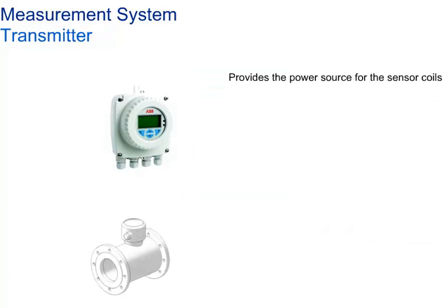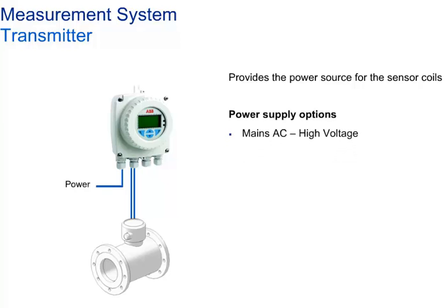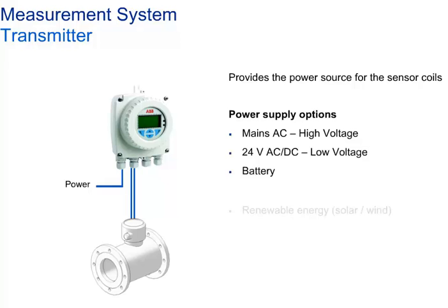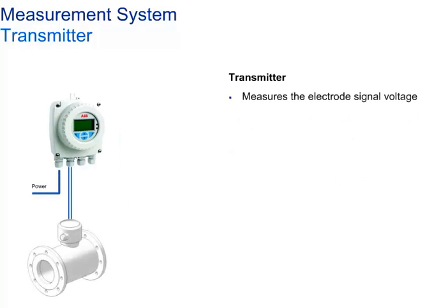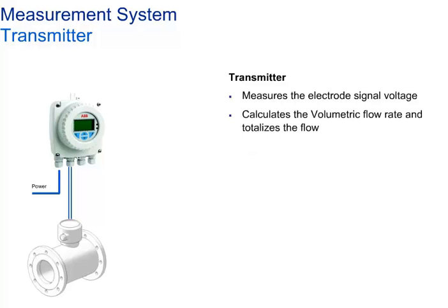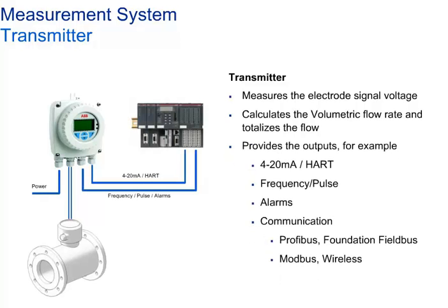The transmitter provides power to the sensor coils. Power supply options include 85 to 253 volts mains AC, 24 volts AC/DC, battery, or renewable energy such as solar or wind. The transmitter measures the electrode signal voltage, calculates volumetric flow rate and totalizer values, and provides outputs as required by the customer.